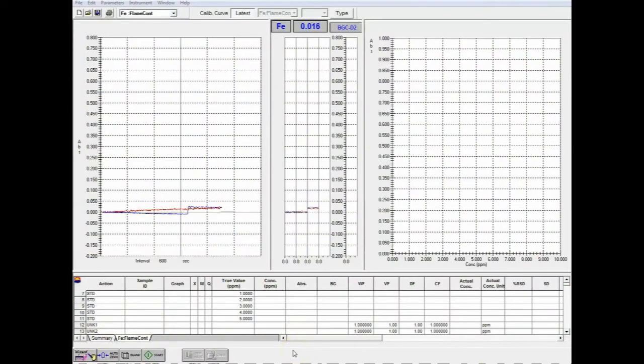So now that our flame has been lit, we're ready to start our analysis. So the first thing we're going to do is auto zero the machine. So we'll see how up here we have some numbers. We want that to be 0. So we'll hit auto 0. And that should set that back to 0. It will fluctuate a little bit, but it'll be fairly close to 0. And now we can start by running our blank.